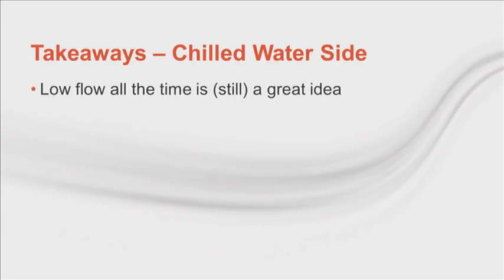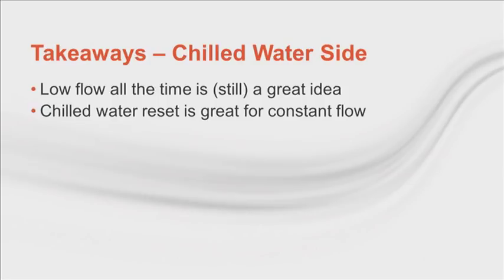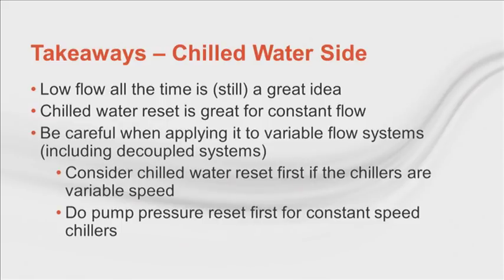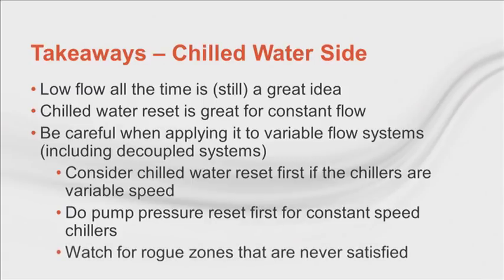Susanna covered the power of lowering the flow rates, whether all the time when the flow is constant or some of the time in the case of variable flow systems. For controls optimizations, chilled water reset can be a powerful optimization tool when done in the right application and not too much, and it's the only game in town for constant flow systems. In variable flow systems, even with a system design with a 10-degree DeltaT, high flow, chiller speed capabilities may change your optimization. Chilled water reset may be more appropriate to do first with variable speed chillers, assuming they have good compressor speed turndown available. Pump pressure reset is first for constant speed chillers. In both cases, watch the critical valve to make sure it's not always wide open and defeating the logic.